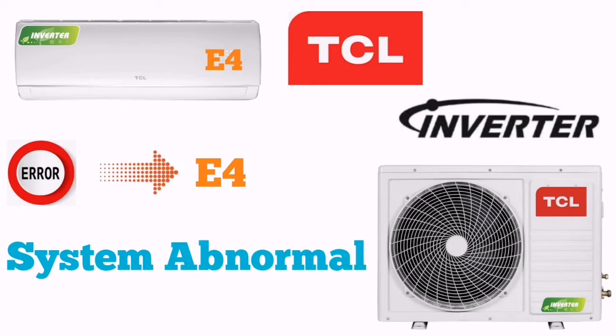Start and run under cooling mode. When the compressor is started, check the outlet temperature for its changes or not. If the change is not done after 5 minutes, the system is short of refrigerant. Test with the pressure gauge, check the leakage point and recharge the refrigerant.